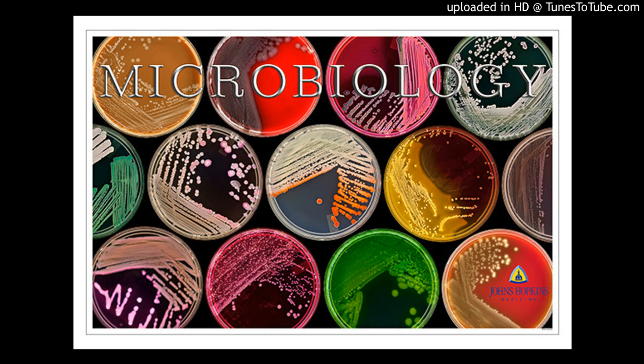The reason why this is the most common approach is because it's pretty cheap to do. Okay? But the problem with using autoclaving is that it can do a lot of disruption to the instruments that you're trying to sterilize. So if it's very thin or electronic or plastic or something like that, it may get warped and weird inside of this guy. So this works well, it's cheap, but you need to make sure that your instruments are stainless steel or heat-resistant plastic, or they will get destroyed.